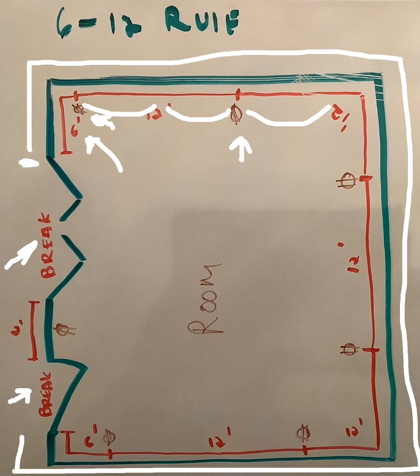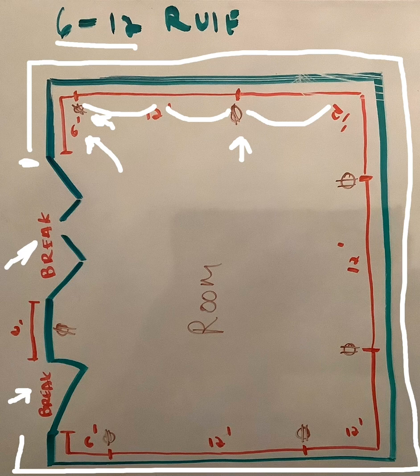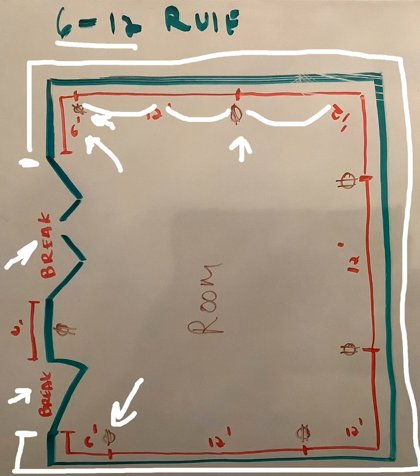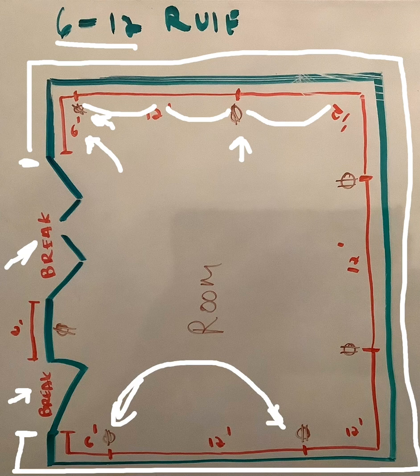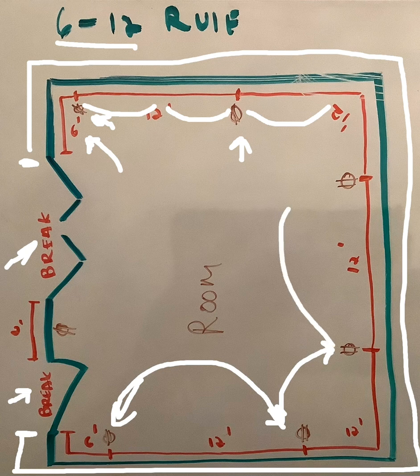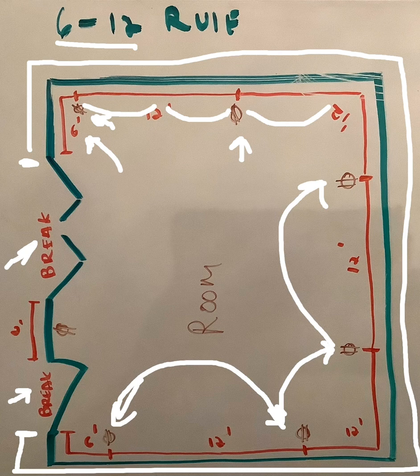To make it simple, we use what's called the 6-12 rule. Each outlet begins within six feet of the edge of a door frame or a break. Then no outlet shall extend beyond 12 feet from the last. And that measurement shall carry around the room as long as it is unbroken by any breaks.